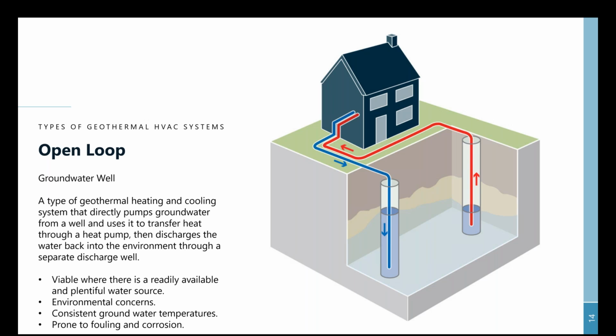And typically those 2 wells are going to be a significant distance from each other so that you don't get any sort of cross-contamination. You would not want to be rejecting heat back into the ground and then it sort of recycles right back into your source well. So obviously this type of system is only going to be viable when there's a readily available and plentiful water source. There are environmental concerns with these types of systems because, again, you are directly taking groundwater out of an aquifer and bringing it into a building.